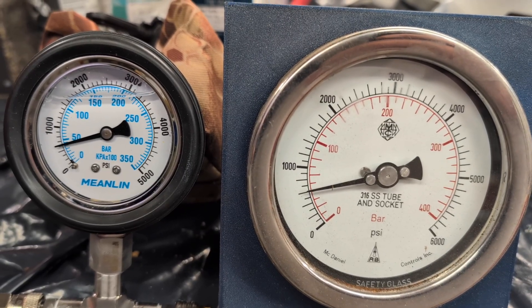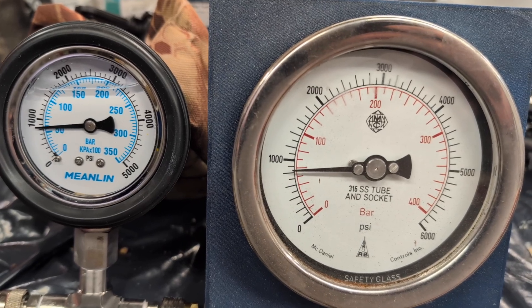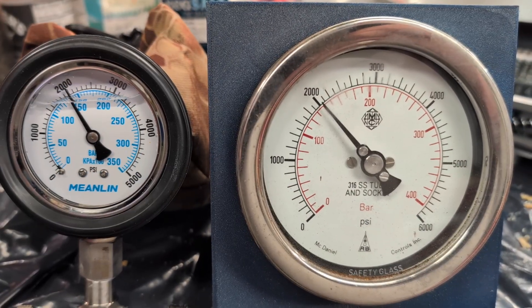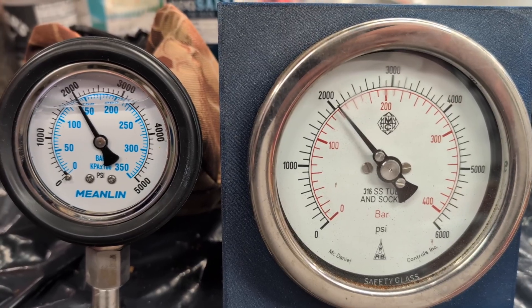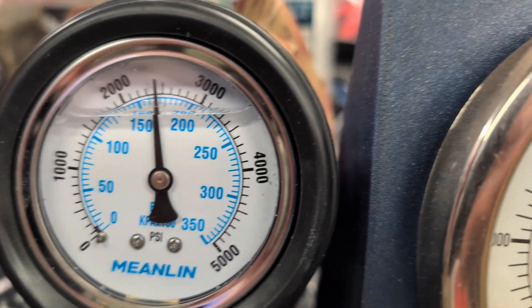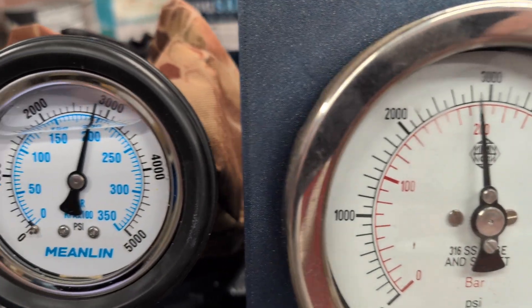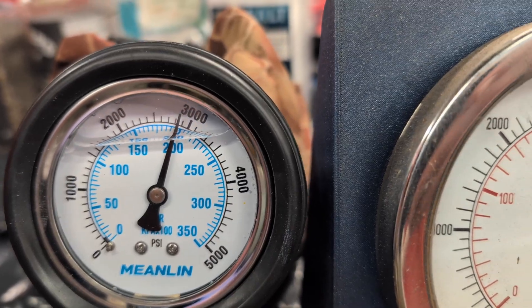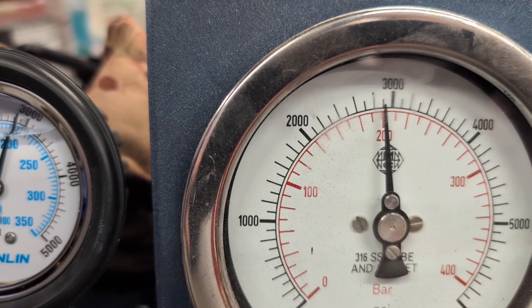Here I'm running this against what I consider my reference gauge — a very large, very expensive gauge out of an industrial plant that I picked up and had calibrated. It is exceptionally accurate, and this new gauge for its price is tracking it exceptionally well. It's just crossing 200 bar and it's right on target. I'm really impressed with this inexpensive Meanlin gauge that goes all the way up to 5,000 PSI.